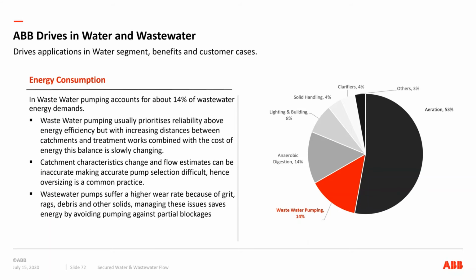When we look at a plant, we've got drives on the blowers and most of the pumps. How can we be more efficient? Putting dissolved oxygen sensors in the aeration basin, flow meters to tell how much flow is coming into the plant, what's my BOD content, what's my nitrate, what's my phosphates, what's my total N contribution, how much do I have to get out of this wastewater. These let us fine tune and control the plant, the VFD speeds, to meet the objectives defined by state and federal standards on nutrients.